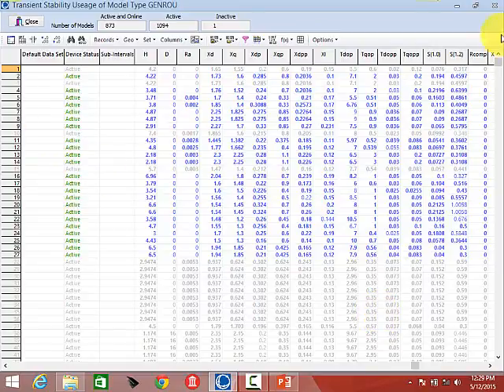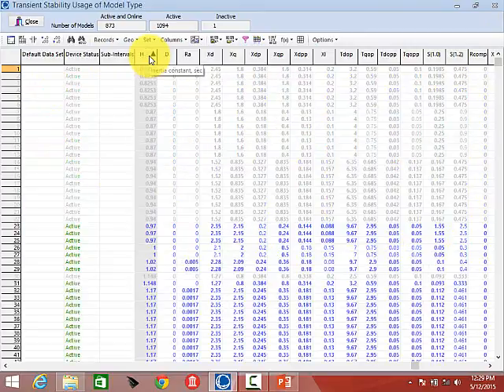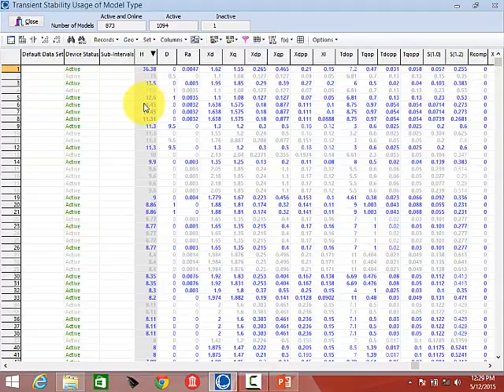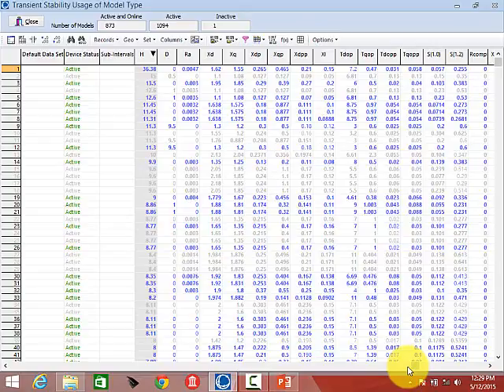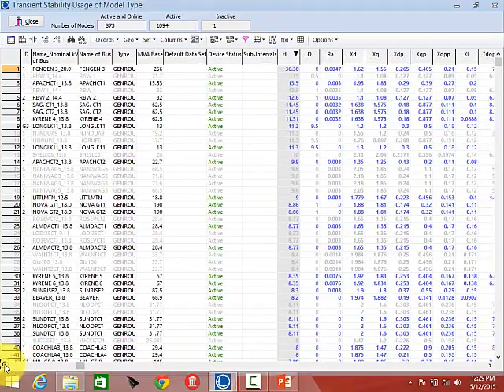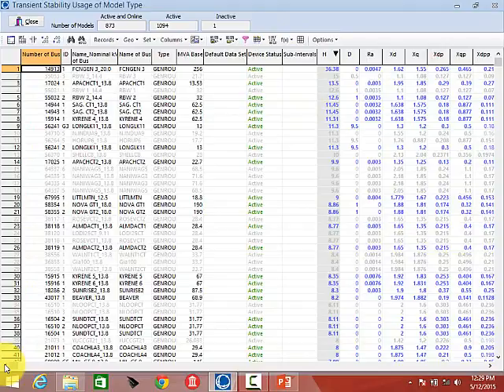For example, if I click on the Inertia H field to sort it high to low or low to high, I can see by sorting high to low that there's one generator with an H of 36 and then the values fall off. Is that data valid? It gives you a feel for the range of data in that display. For instance, bus number 14,913 — maybe it really does have an H of 36. This gives you access to all that data.